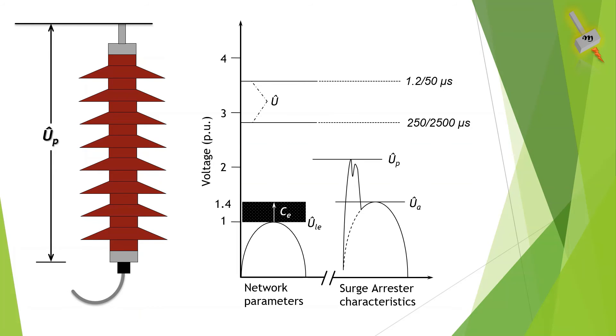But due to the passage of the surge current a residual voltage is developed across the surge arrester terminal. The residual voltage is important considering the fact that it has a direct impact on the system BIL and a sufficient margin needs to be kept while arrester selection.